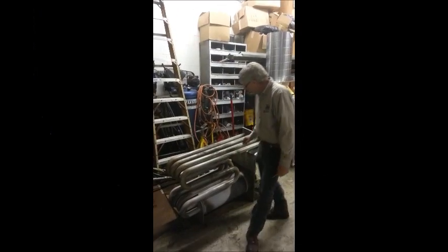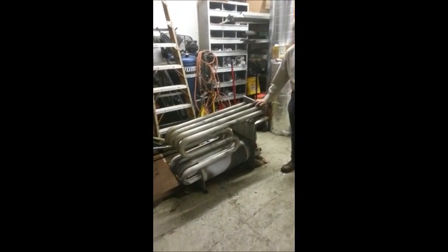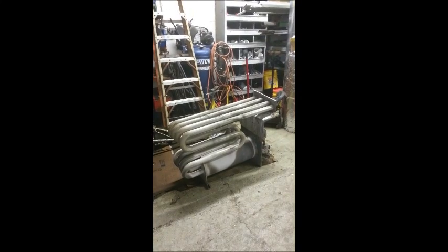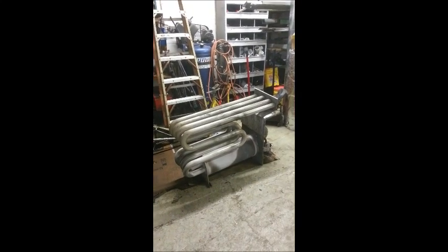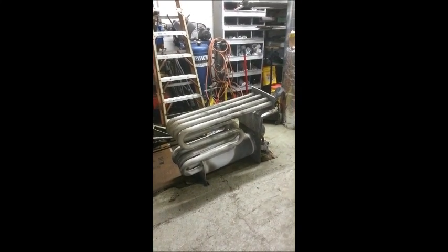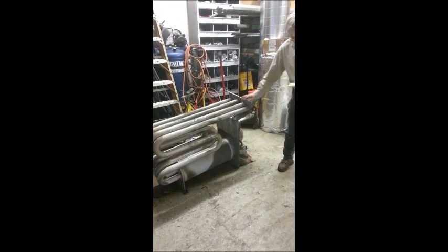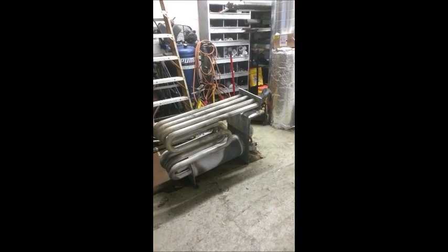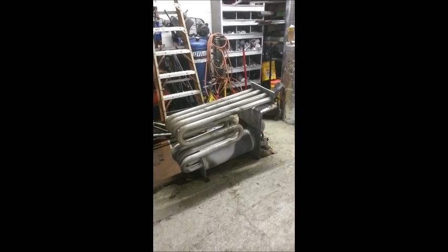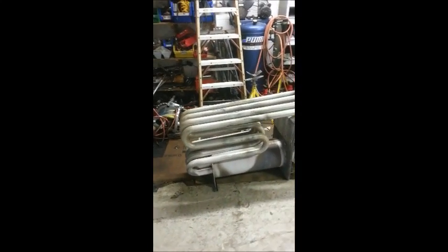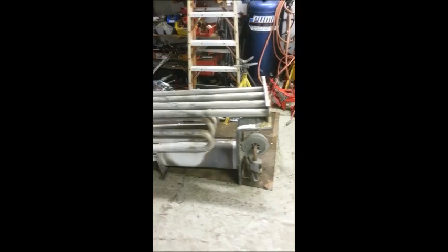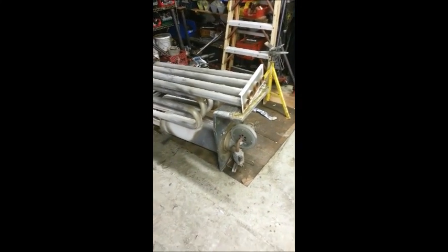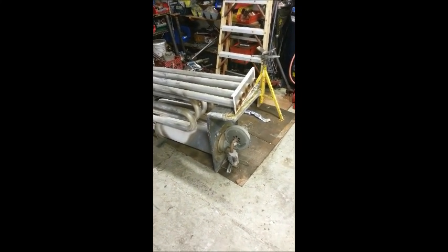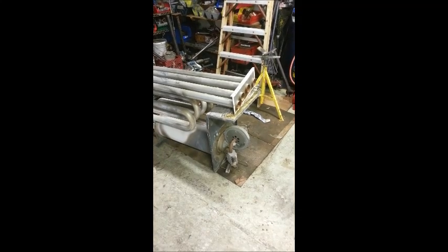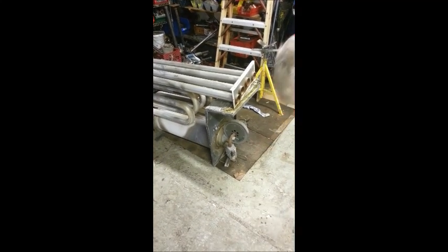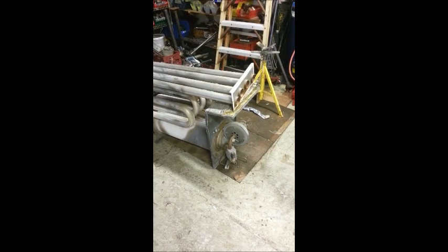Right here we have ourselves a Trane Heat Exchanger. In this brief review, we are going to go over what to look for in the degradation of this style heat exchanger. The Trane Voyager heat exchanger is very reliable, and other than igniters, combustion draft motors, and ignition controls, there are not many components to go bad. I've changed very few of these gas valves over the years, so they are a pretty steady component.